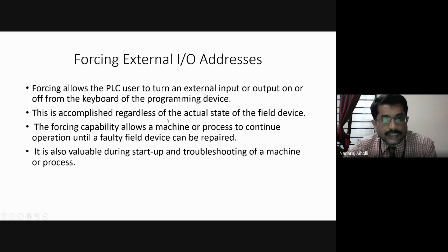This is accomplished regardless of the actual state of the field device. Whatever the state of the field device, either on or off, the user is forcing the external input or output to be either in the off state or in the on state, irrespective of the state of the field device. The forcing capability allows a machine or process to continue operation until a faulty field device can be repaired. Now, what is done here? Here, the field device may be either on or off, it doesn't matter.